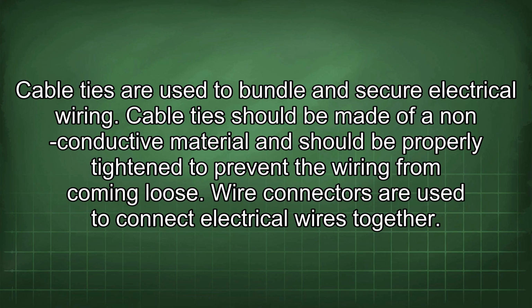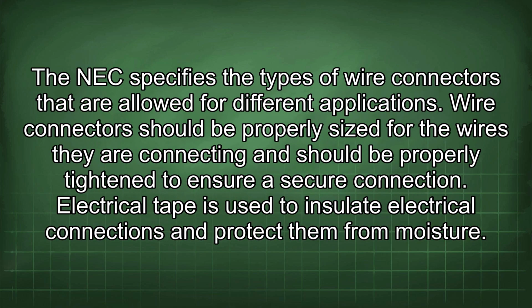Cable ties are used to bundle and secure electrical wiring. Cable ties should be made of a non-conductive material and should be properly tightened to prevent the wiring from coming loose. Wire connectors are used to connect electrical wires together. The NEC specifies the types of wire connectors that are allowed for different applications. Wire connectors should be properly sized for the wires they are connecting and should be properly tightened to ensure a secure connection.